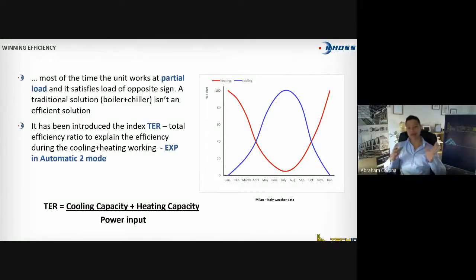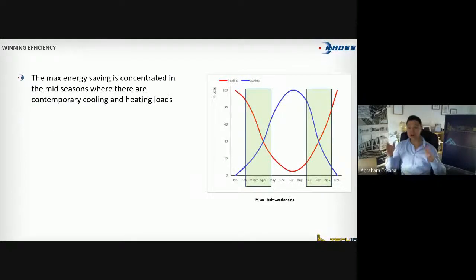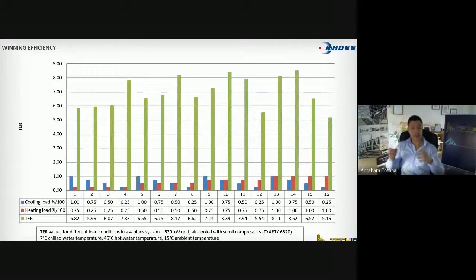So the graph you see on the right is, sorry, European weather data. I got lazy, I copied from the European presentation, but the behavior will be something similar. In any country, you have the 4 seasons separated, unless you go to the tropic area. And that means when you are in the middle season, that you're producing hot water and chilled water at the same time, is when you have your period of better efficiency, because you are reducing that energy you were wasting before. If you are only cooling and you have a demand for heating, you're wasting that energy and vice versa. I think this graph gives you a better idea of what happened there.